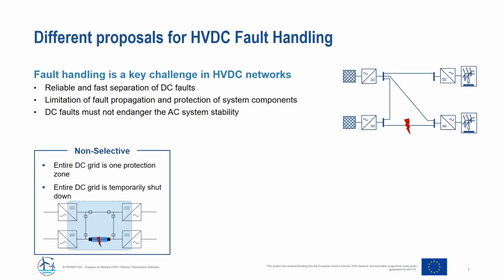In general, fault handling is a key challenge in HVDC networks. We need reliable and fast separation of DC faults, a limitation of the fault propagation, and the protection of the system components in case of a fault. And in general, the DC faults must not endanger the AC system stability, especially when it comes to larger HVDC grids. So there are different strategies proposed for these systems with new components, and I will only give a brief overview here. For more detailed presentations, I'd like to refer you to work packages 4, 5, 6, and 10 on the different components and strategies.